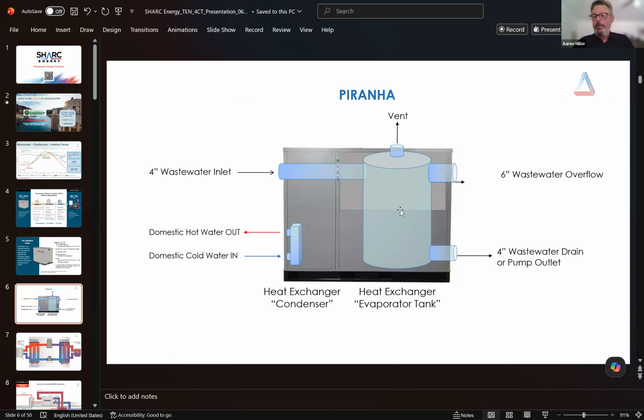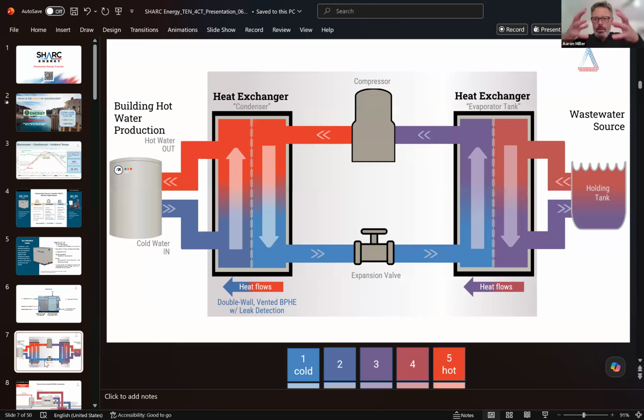The trick is we're trying to fill this tank up with that 70-some-odd degree water that comes out of a building year round. And then we're slowly extracting the energy out of that wastewater into the refrigerant that's passing around that tank. Then we run that warmed refrigerant through a compressor. This is just standard heat pump 101. Refrigerant through a compressor into a brazed plate heat exchanger.